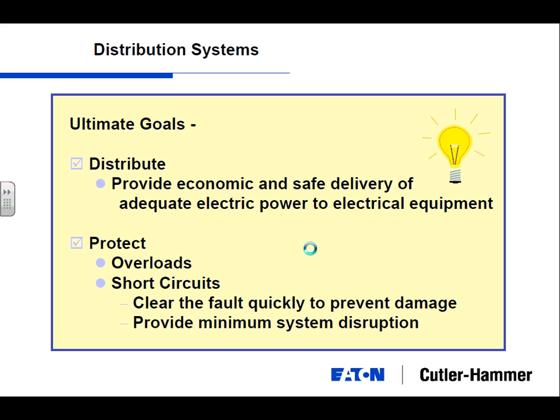So if a wire is rated for 100 amps, you're looking at the size of the copper, the diameter of the copper that's in that wire, and the insulation around it. And the more amps you run through there, from 100 amps up to 200 or up to 400 or up to 600 amps through this 100 amp wire, it's almost the same as opening up a fuse. It's copper that, as it gets hotter, is going to lead towards failure. Short circuits are also a failure mode, but rather than an overload, which is a lower current over a longer time, a short circuit is a higher current over a shorter time.